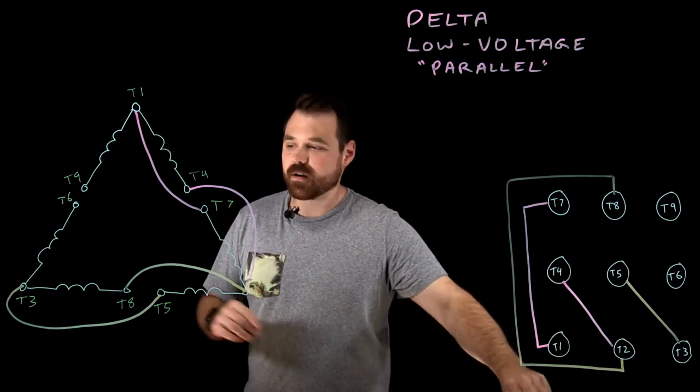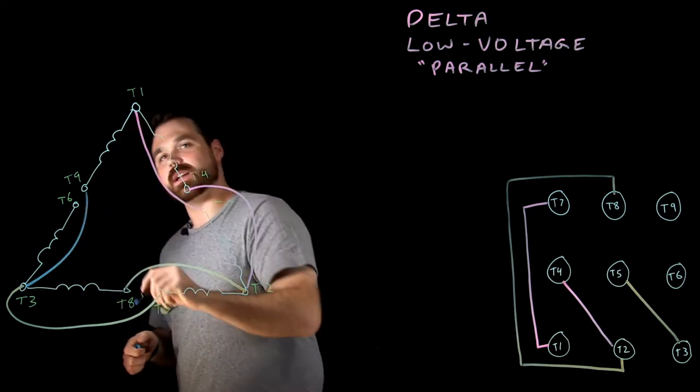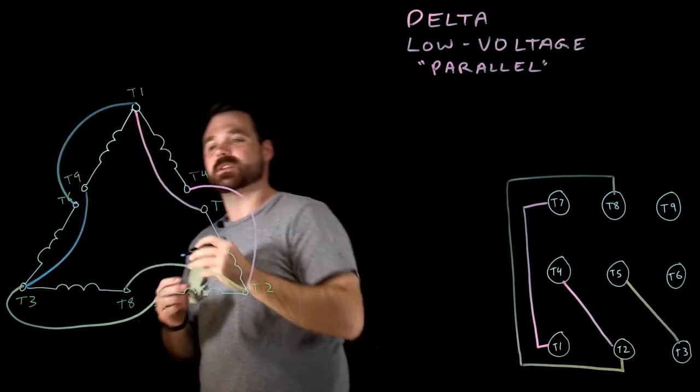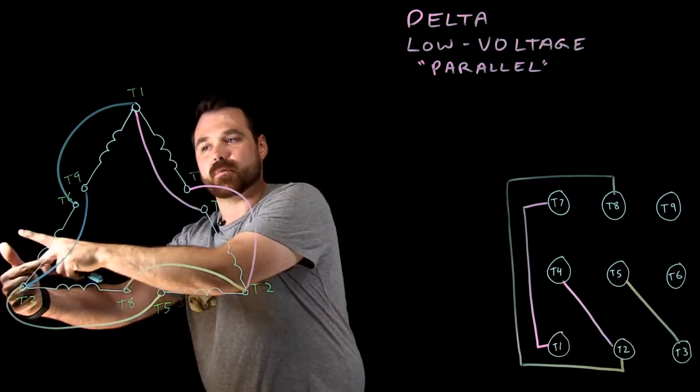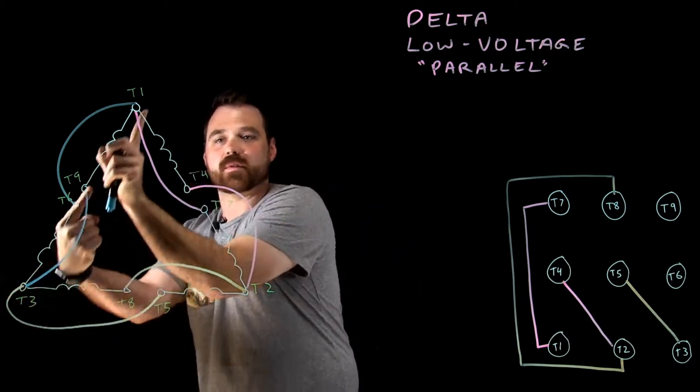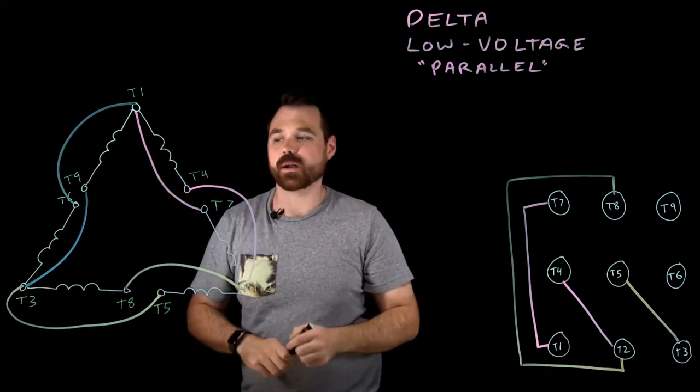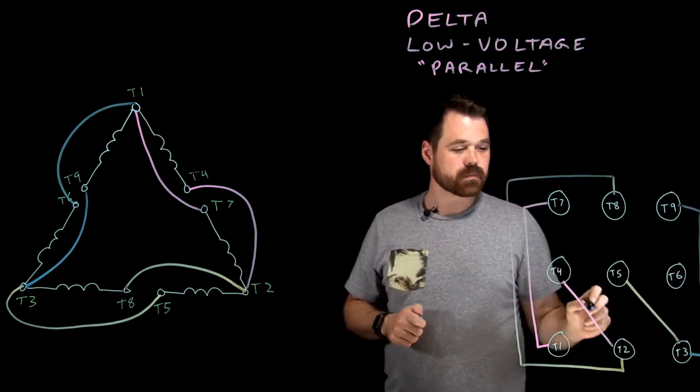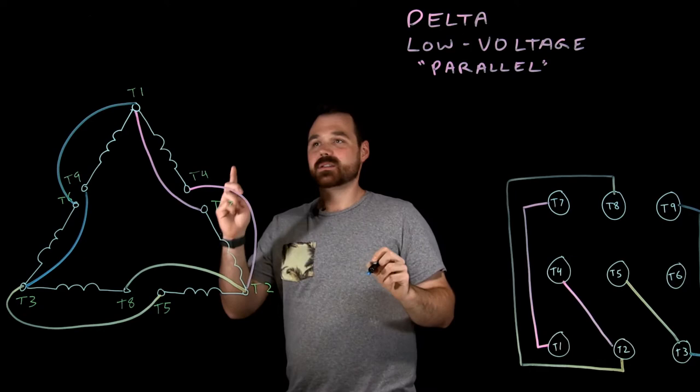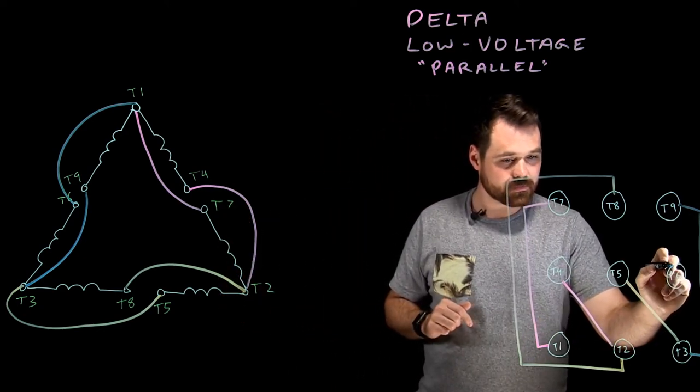We get into our very last connection here, which would be T3 to T9 and T6 up to T1. Again, current flows into T3, then it would also be flowing into T9, current flowing the same direction through both of those windings, which is what we want. So we have T3 to T9 and T6 to T1.